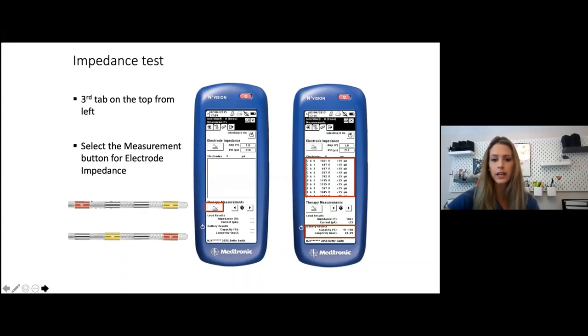We're looking for it to be greater than 50 ohms and less than 4,000. If it's within that range, you won't have any combinations highlighted, just like this picture shows. However, if you do have an impedance that's out of that range specified, then it will highlight black, notifying you that this impedance is off.